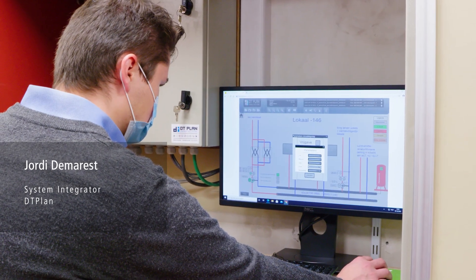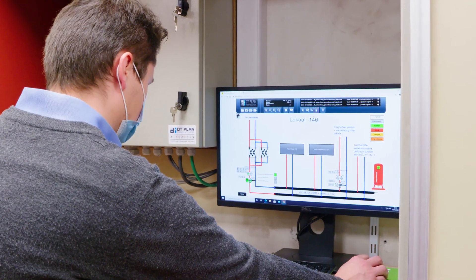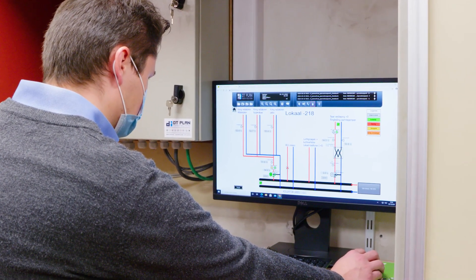We replaced the old control system with a new building management system from Beckhoff Automation. The biggest challenge of this project was that the old building system had to continue to operate while we made the changes. As the old system was still running, we removed the bus cables, commissioned the Beckhoff controllers and kept the old system in function. The day after, we connected the new Beckhoff controllers step by step, and the total downtime of the system was basically zero.